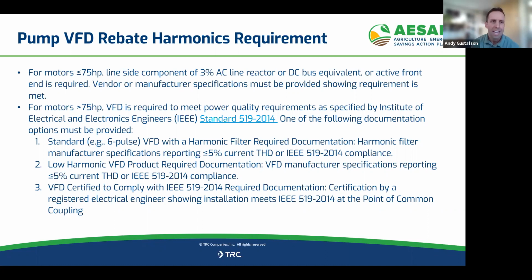If it's less than or equal to 75 horsepower, a line side component, a 3% AC line reactor, or DC bus equivalent or front end, is required. So what does that mean if you're going to submit a rebate? We need the vendor or manufacturer specs, or some other documentation, provided to show that the requirements are met. For greater than 75 horsepower, it's required to meet the IEEE requirements as linked here.